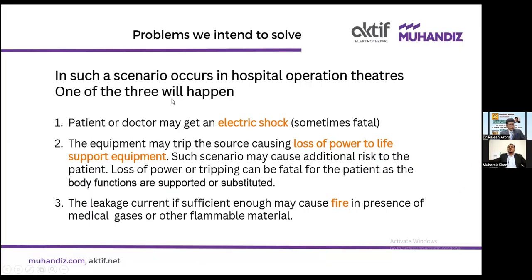These scenarios normally happen everywhere, but what will happen if it happens in a hospital operation theater? The patient or doctor may get an electric shock. Sometimes it will be fatal. Equipment may trip the source, causing loss of power to life support equipment. Such a scenario may cause additional risk to the patient. Loss of power or tripping can be fatal for a patient whose body functions are supported or substituted with medical electrical equipment. Leakage current, if sufficient, may cause fire in the presence of medical gases or other flammable materials.